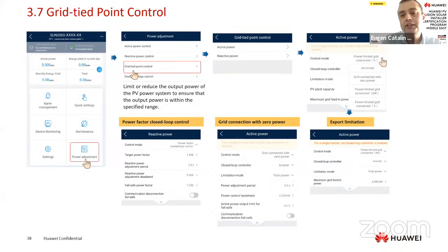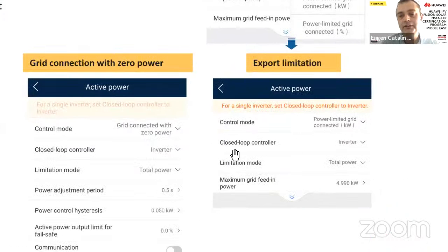Power limited grid connected. This means that I will put, I don't know, half of the production to go to the grid and half for the consumption, or in percentage. As I said before, using this function, export limitation or other functions, we'll have a closed loop controller here. You see this option. If I have only one inverter, it will be like this. If I have a cascading scenario with a dongle, I need to choose this closed loop controller smart dongle.